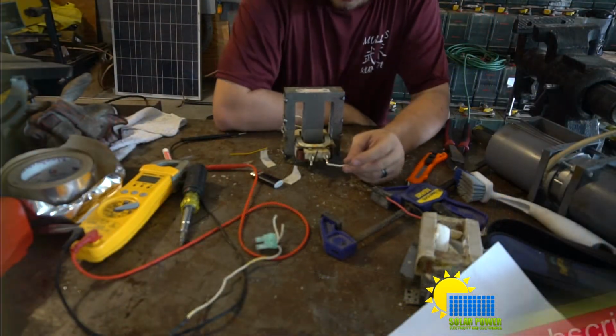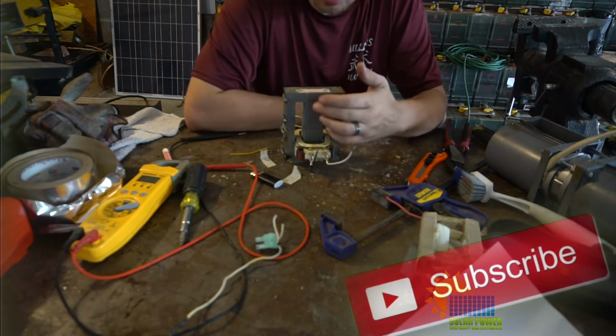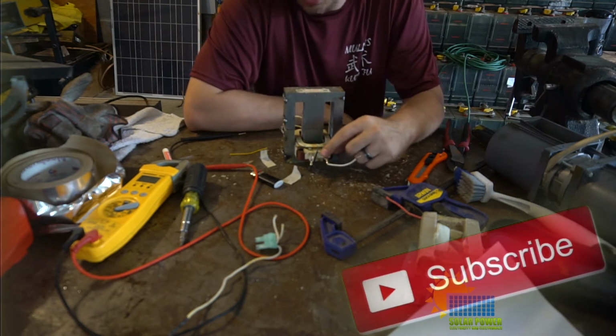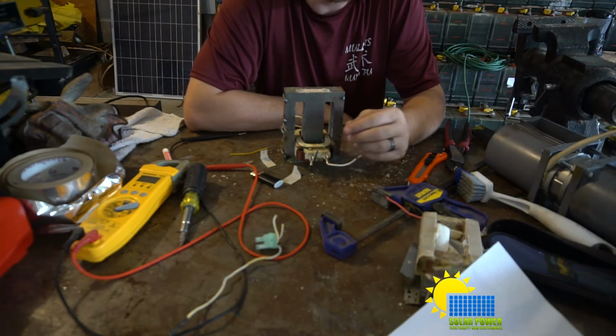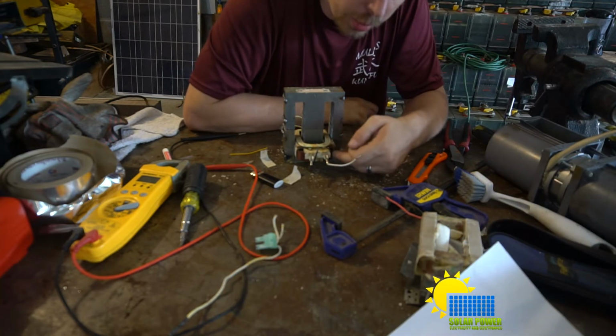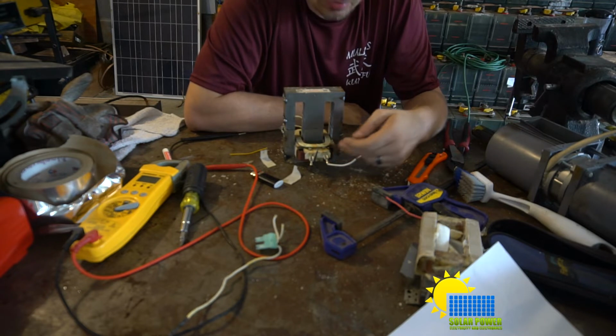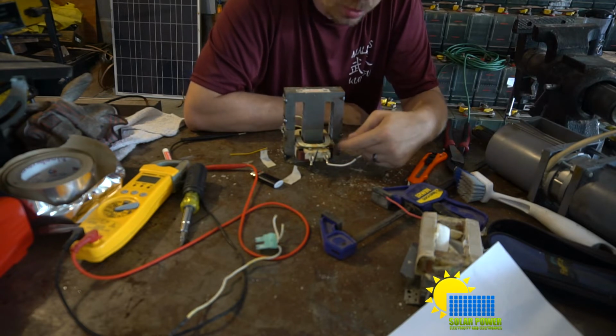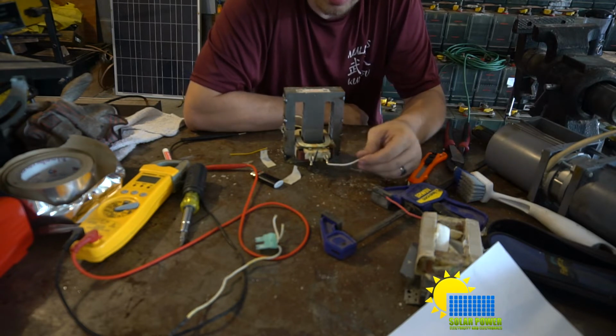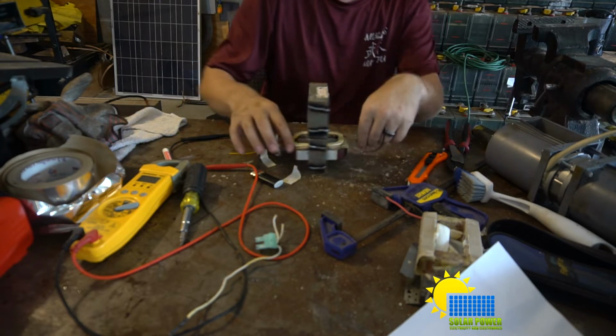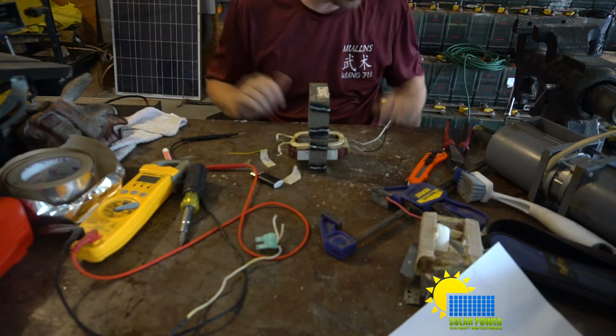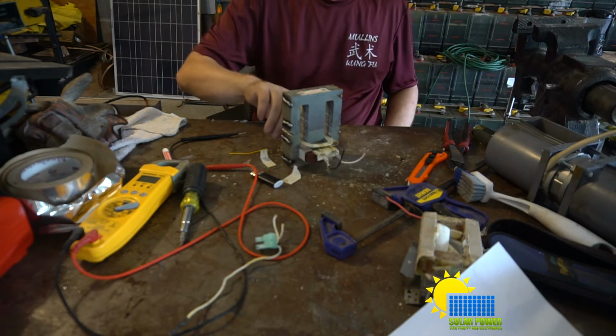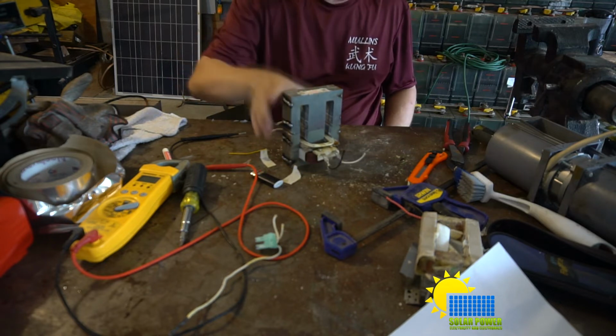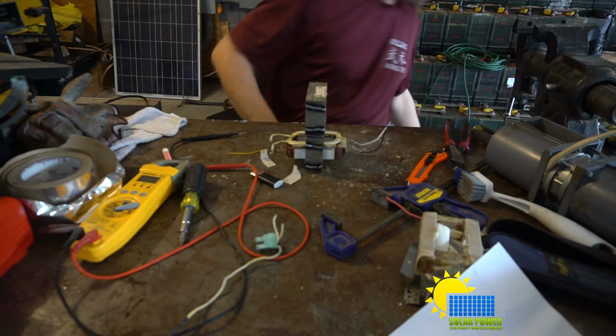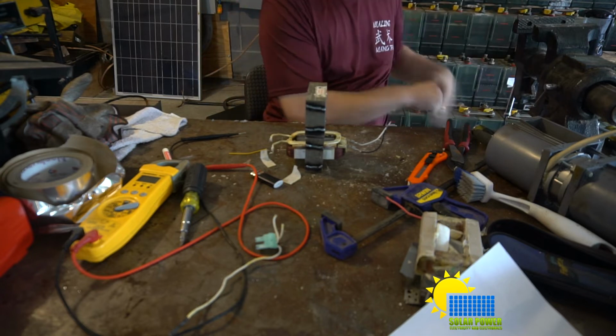Now, to properly do this, you're going to want to attach a white wire to a screw here. The reason why is in case this coil goes bad and touches this piece of metal here, you won't get shocked when it does. But I'm just going to test it, and remember, this table is conductive, so I won't touch it directly. I'm just going to test the transformer on top by plugging it directly into an extension cord.